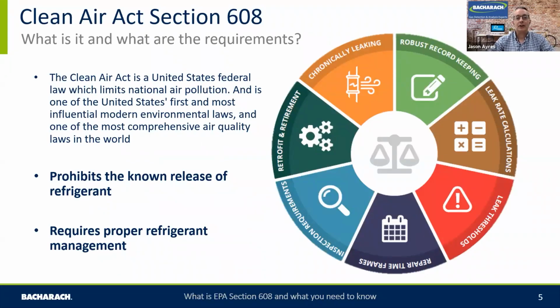The Clean Air Act is a United States law which limits national air pollution. To be honest, it's been one of the most successful US laws and influence in modern times. And it's a very comprehensive air quality law and one of the best in the world. In terms of EPA 608, it's targeting refrigerants and those emissions to the atmosphere. Really, its pillars are looking at prohibiting the release of refrigerant. So that's in the terms of maintenance, repair, new system, and also really targets the proper refrigerant management of the system. So the recording, the capturing of the information and having that information available to the EPA in case of any auditing. It really does focus on leak prevention and record keeping, and they are the really fundamental pillars of the 608.